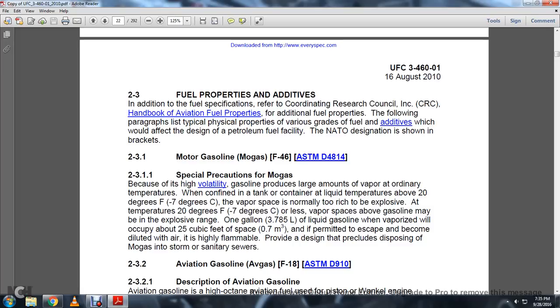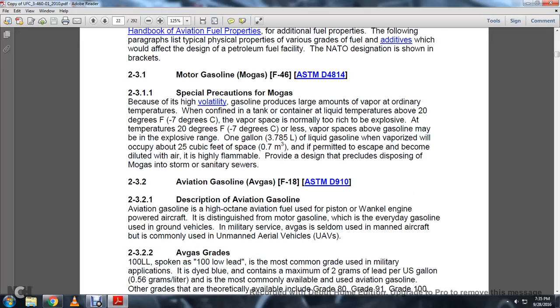Special precautions for MOGAS: because of the high volatility, gasoline provides large amounts of vapor. Ordinarily, at ambient temperatures combined with tank liquid temperatures above 20 degrees Fahrenheit, the vapor space is normally too rich to be explosive. At a temperature of 20 degrees Fahrenheit, the lower vapor space above the gasoline may be in the explosive range. One gallon of liquid gasoline would vaporize to about 25 cubic feet of vapor, and if permitted to escape, it becomes diluted with the air. Because of high flammability, provide a design that precludes disposing of MOGAS in the storm or sanitary sewers.